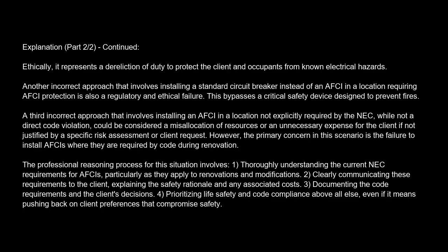A third incorrect approach that involves installing an AFCI in a location not explicitly required by the NEC, while not a direct code violation, could be considered a misallocation of resources or an unnecessary expense for the client if not justified by a specific risk assessment or client request. However, the primary concern in this scenario is the failure to install AFCI where they are required by code during renovation.